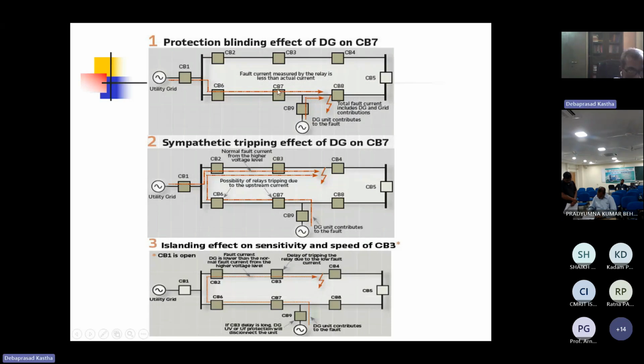This is called the protection blinding effect. The opposite thing can also happen. Suppose the fault is on this side. Now not only the utility grid, but this DG will also feed the fault. As a result, one of these circuit breakers can trip. Now the third situation is where there is a fault and CB1 has disconnected. But now the fault is being fed by the DG and the DG current does not exceed a certain maximum limit. So the point is CB3 may take longer to trip.